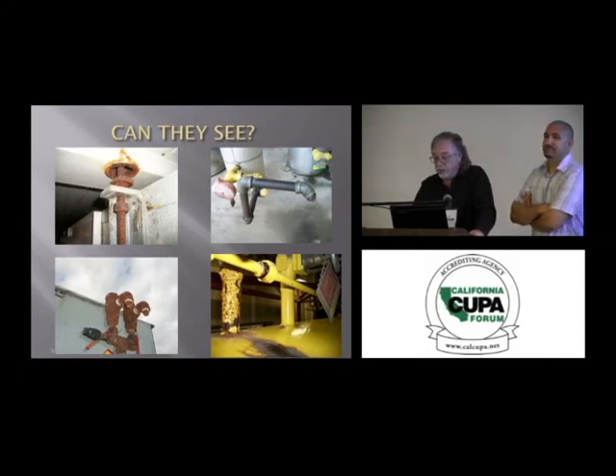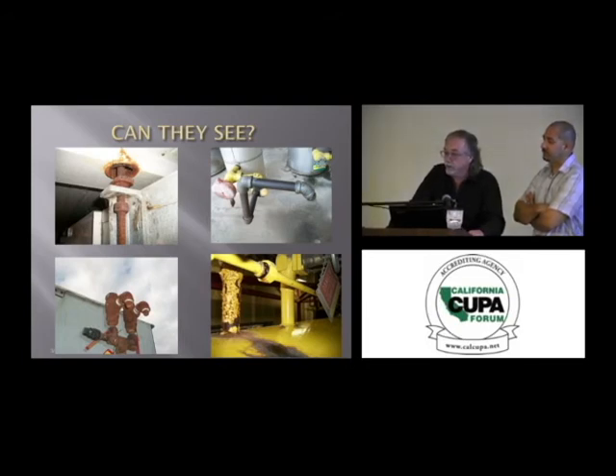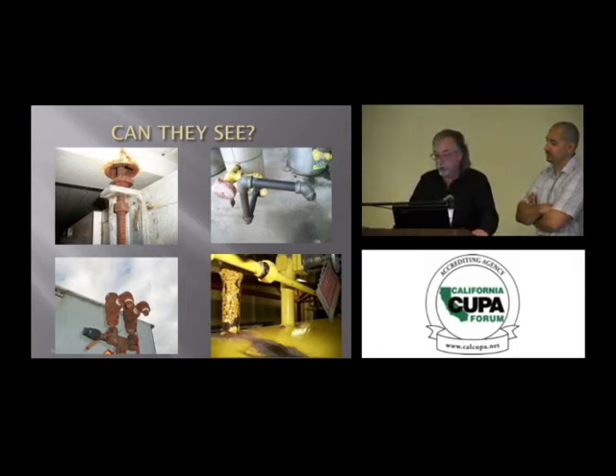Yeah, they're galvanized. That's on an oil drain. Even though it's after the oil drain valve, guys will use just about anything on that. It's a good practice not to be using any incompatible materials at all. Okay? There's no pressure. There should be no ammonia on that, except for when you're draining oil. But still, it's incompatible.